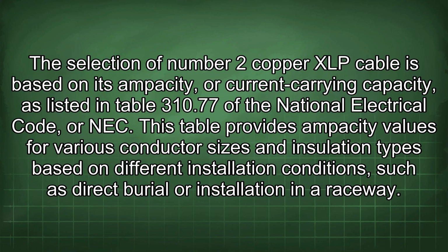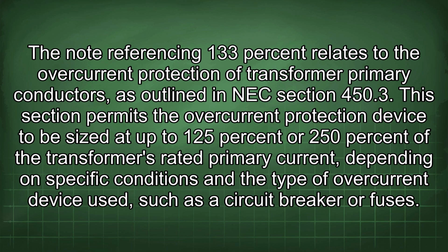The selection of number 2 copper XLP cable is based on its ampacity, or current carrying capacity, as listed in Table 310.77 of the National Electrical Code, or NEC. This table provides ampacity values for various conductor sizes and insulation types based on different installation conditions, such as direct burial or installation in a raceway. The note referencing 133% relates to the overcurrent protection of transformer primary conductors, as outlined in NEC section 450.3. This section permits the overcurrent protection device to be sized at up to 125% or 250% of the transformer's rated primary current, depending on specific conditions and the type of overcurrent device used, such as a circuit breaker or fuses.